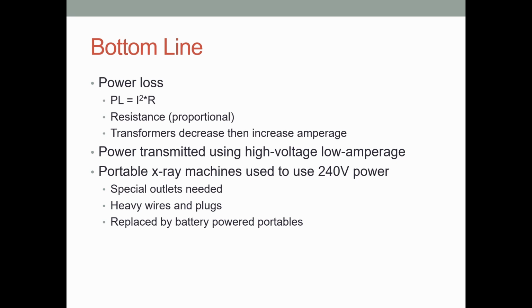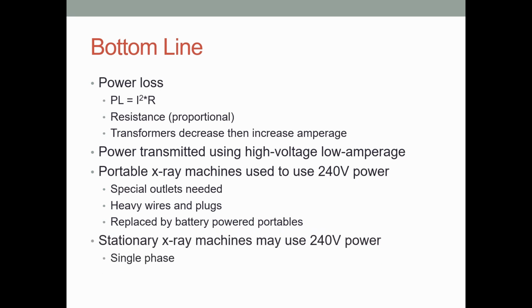Stationary X-ray machines mostly use 240-volt power. It may be single-phase like is depicted in this presentation, or three-phase to provide a more homogeneous X-ray beam.